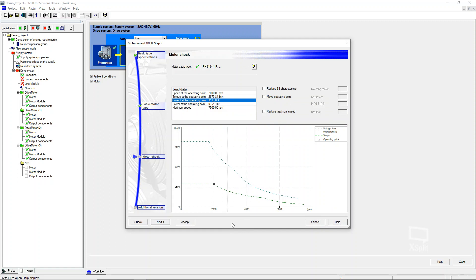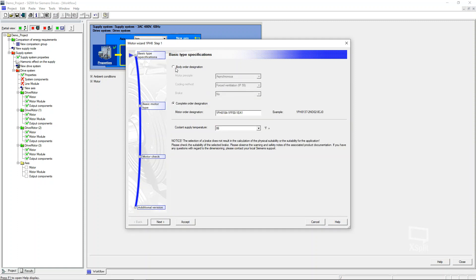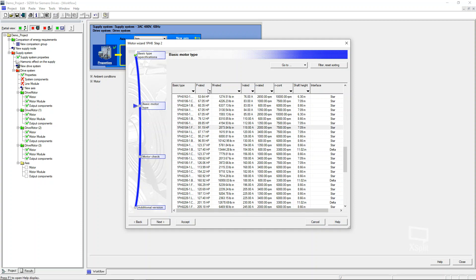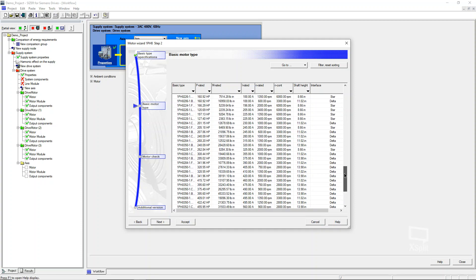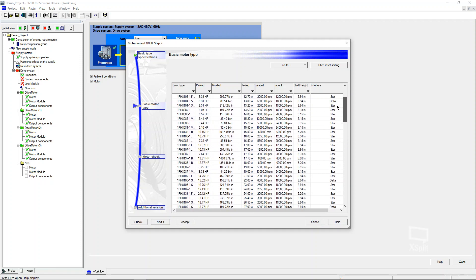If you have an actual full part number, let's go back and take, click back two times. And then look at this body order designation, because you can actually use this sizer tool to kind of select. If you know how much torque you are wanting, how much you've done a calculation on your inertia, maybe you've modeled your machine up into SolidWorks and you know how much torque you're going to need in order to get the cycle that you want. You can go into body order designation here and you can go and kind of select from a table. We're just going to look at the asynchronous motors, the forced ventilation IP55 is your standard stuff, and then without a holding brake. We're just going to click next and bring up this list here. So these are the entire list of the 1PH8 motors that meet those specifications.